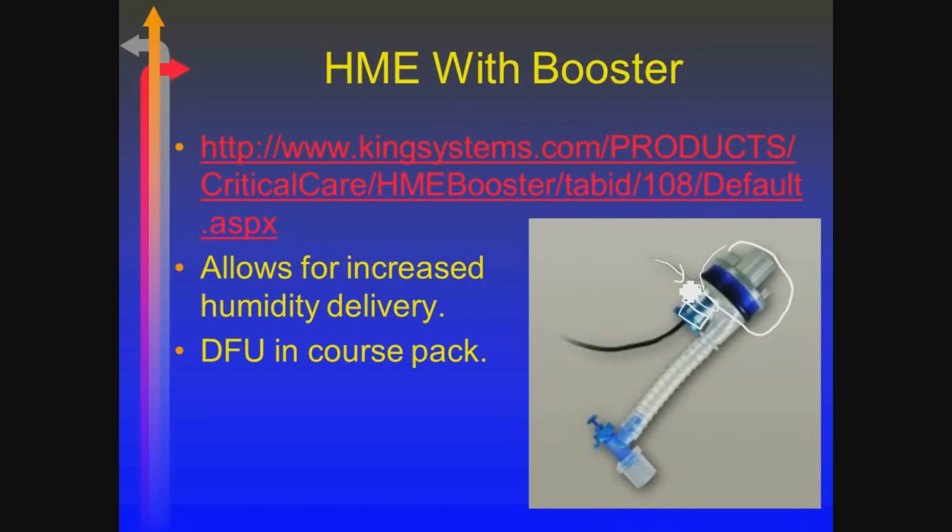And what it does is it slowly drips some water onto the surface of this heater and adds some additional humidity. It's on the side that's going to the patient, and when we go through it in the lab, it says right on it, patient, so you know which side to hook up to your patient connector, and what side goes on the Y.